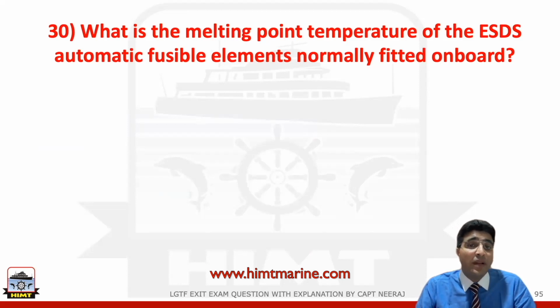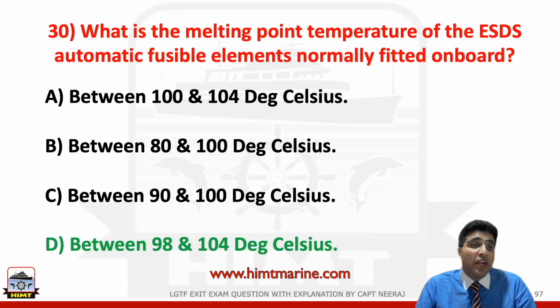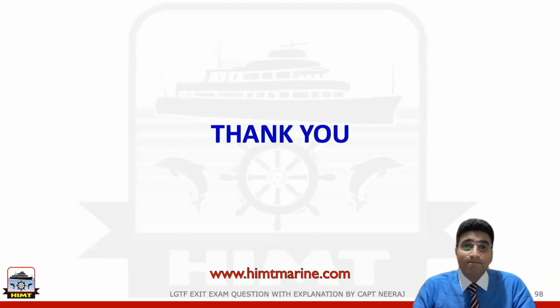In case of fusible elements, which look something like this, what you are looking at on top is basically an electrical link and the bottom one is a pneumatic link. These are designed to operate between a temperature of 98 and 104 degrees Celsius, not below this and not above 104 degrees Celsius. So the correct choice for question number 30 is option Delta, between 98 and 104 degrees Celsius. So this brings us to the end of our discussions.